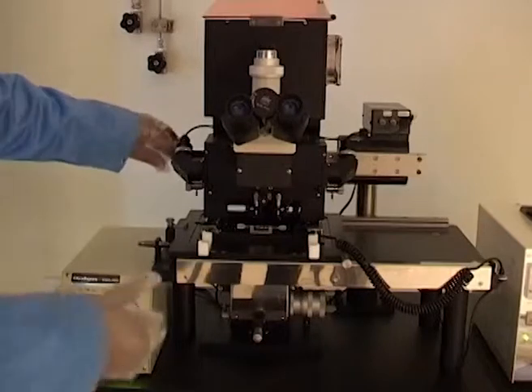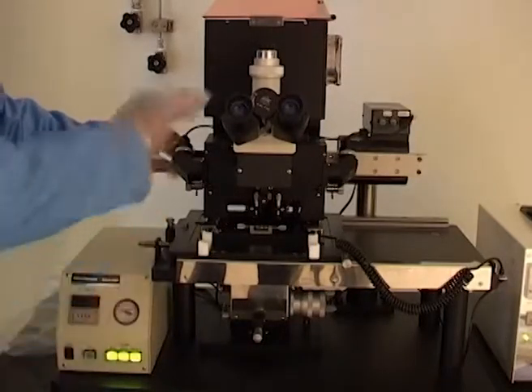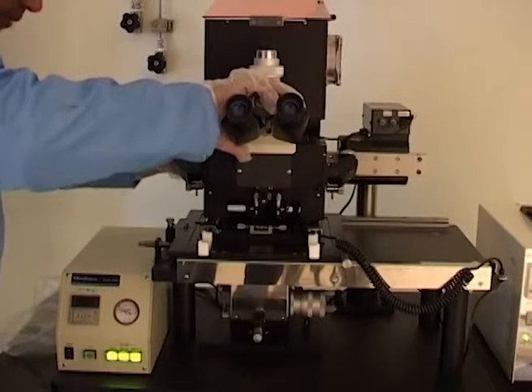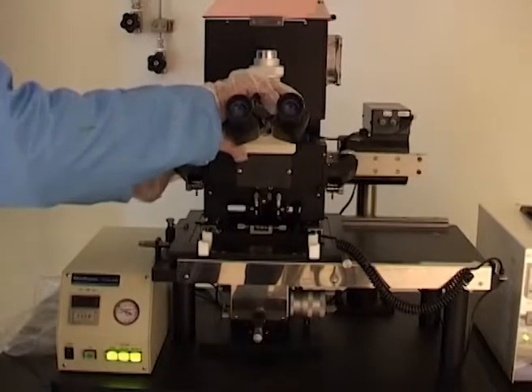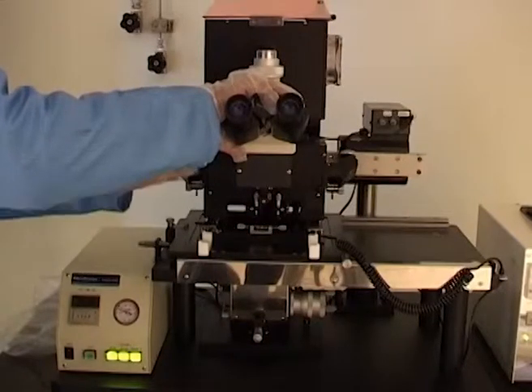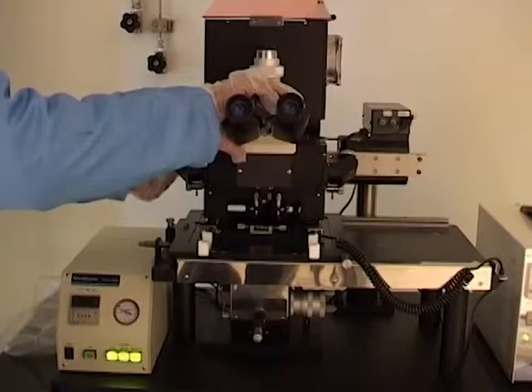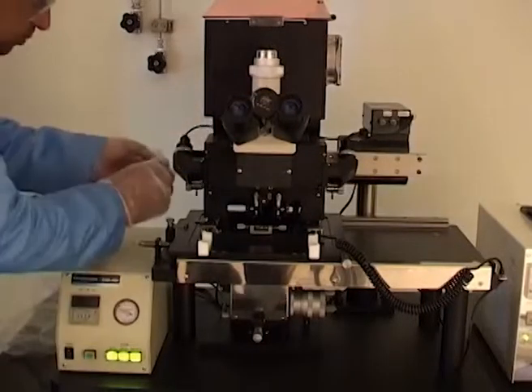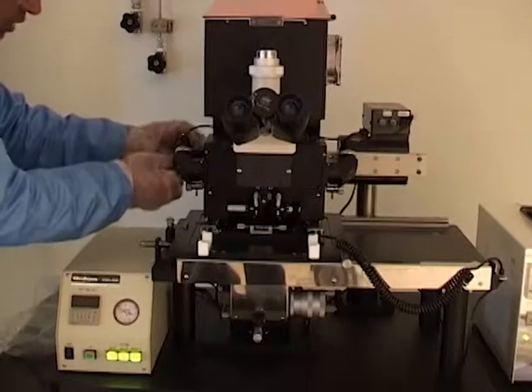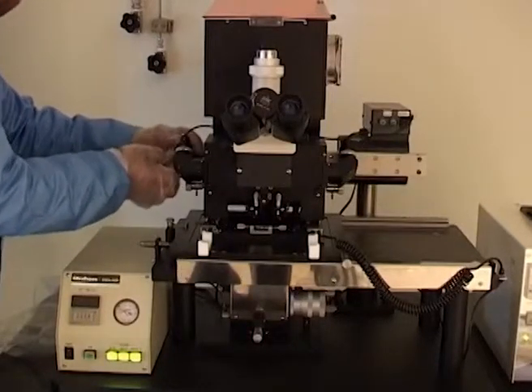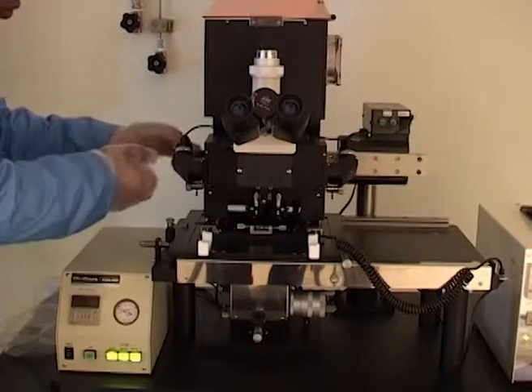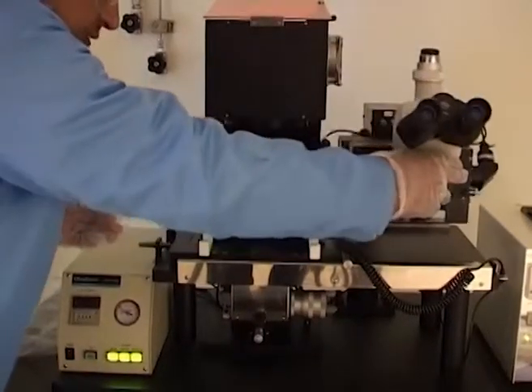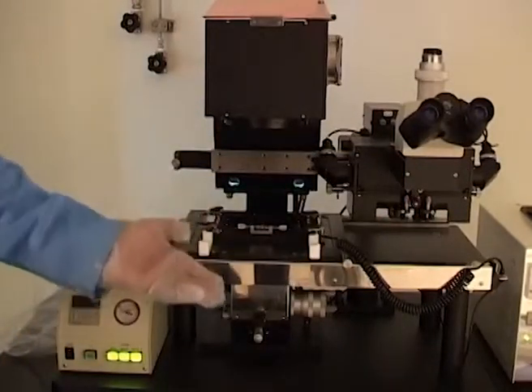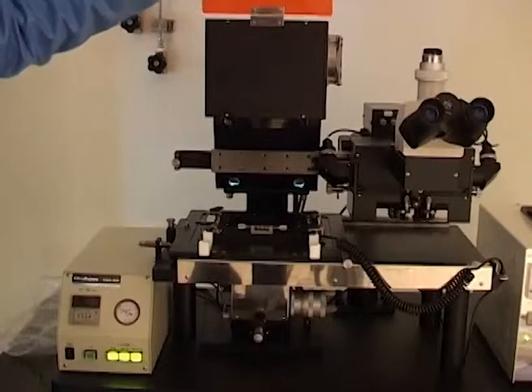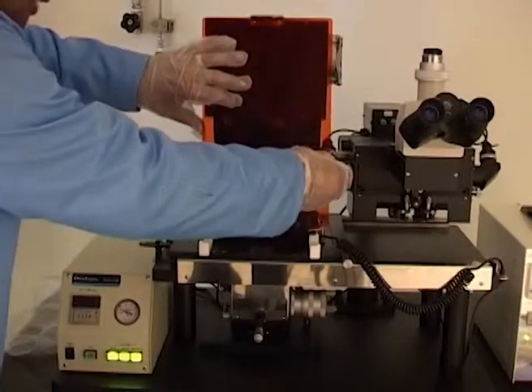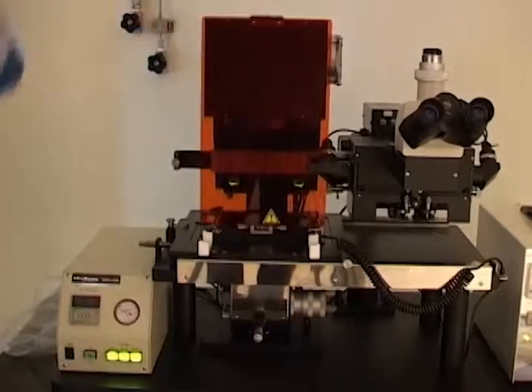So now after all this exposure time setting etcetera has been done, we need to take care of this microscope stage by moving it back, because now we also need to do exposure. Essentially I am going to unbolt this whole stage from here and then shift it slightly towards the right and dock it in its position, and that is going to give me a through pass for the UV light to go through the mask and fall onto the wafer surface. So this is now taken care of. The mask is in contact with the wafer, and in order to protect the operator, there is a UV shield which has to be installed here before doing the exposure, and we are all set to do the exposure.